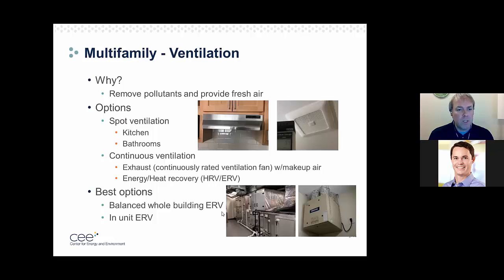So best options here are balanced whole building ERVs. I'll show an example in a case study we'll go over, but that's about a huge room that machine took up for a 59 unit apartment building. Definitely the best, easiest to service, change filters and maintain it, being away from the units. The one drawback of this type of system is the huge upfront cost of the box itself, and also running that ductwork to each unit is going to be quite a large cost up front.